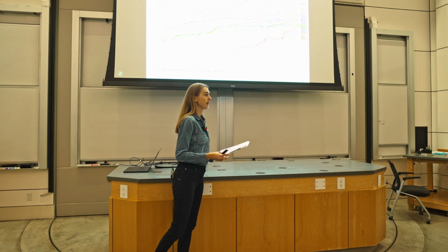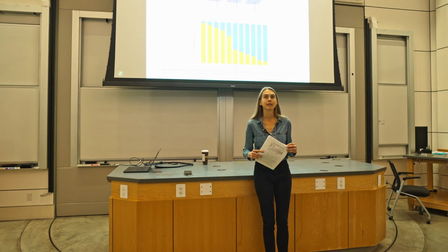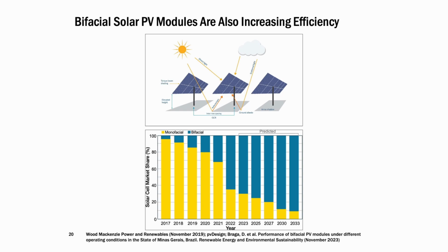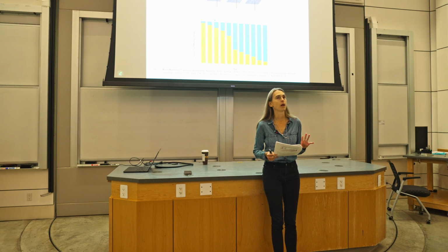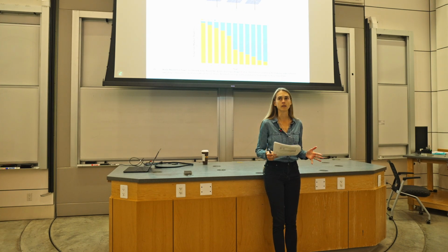But definitely something to keep an eye on as research on these continues. Another big and recent innovation that's happened in solar PV is what's called bifacial solar panels using PERC technology. And effectively what that does is puts PV technology on the back of solar panels to capture additional reflected and refracted light. The result is that bifacial PERC technologies can increase a PV panel's productivity by 10 to 15%.